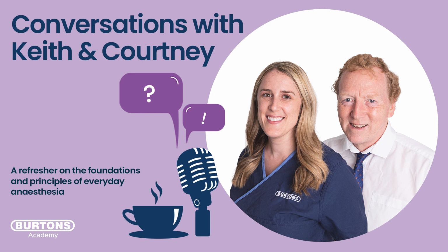So I think if we had to visualize it, visualize a 3-way tap that has a port at 3 o'clock, 12 o'clock, and 9 o'clock. Normally, in normal operation, getting signals from our patient to the transducer off to the machine, we have ports 3 and 9 o'clock open, because 3 o'clock is where our saline bag is connected, and 9 o'clock is the line, like a drip line, but it's not just a simple little piece of extension line going from our transducer to our patient. That's usually always open, that 3 till 9, to get our readings.